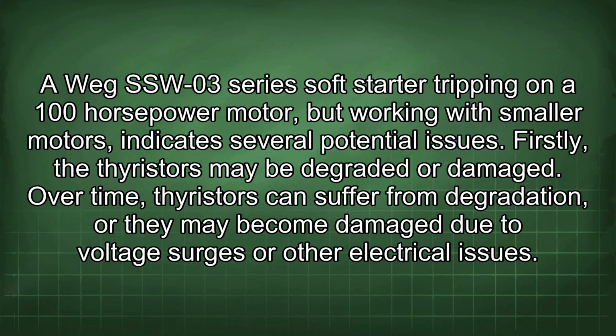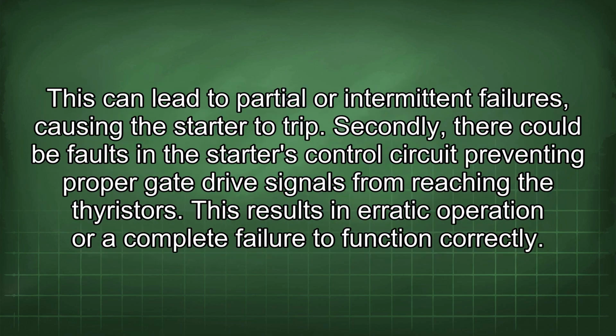A Weg SSW-03 series soft starter tripping on a 100 horsepower motor, but working with smaller motors, indicates several potential issues. Firstly, the thyristors may be degraded or damaged. Over time, thyristors can suffer from degradation, or they may become damaged due to voltage surges or other electrical issues. This can lead to partial or intermittent failures, causing the starter to trip.